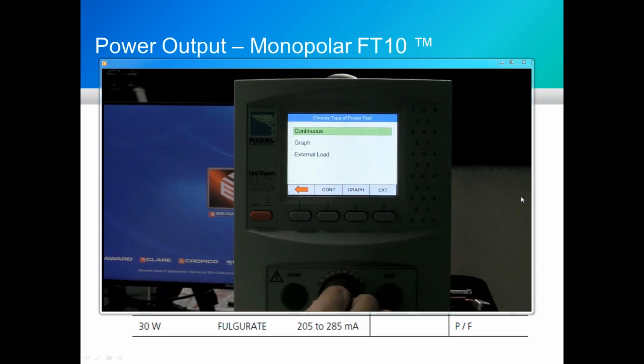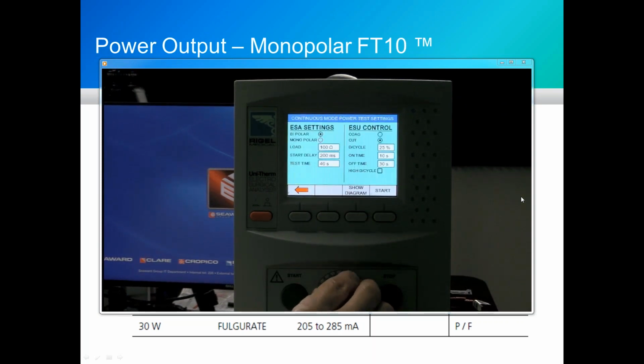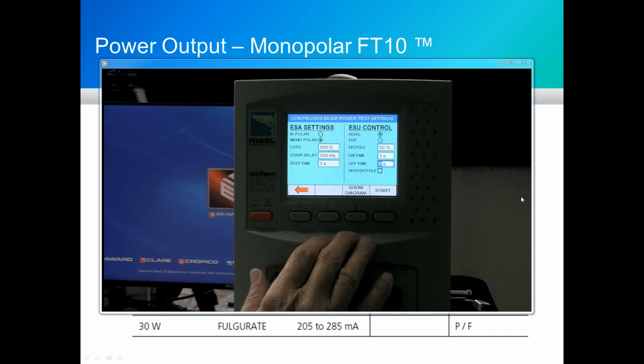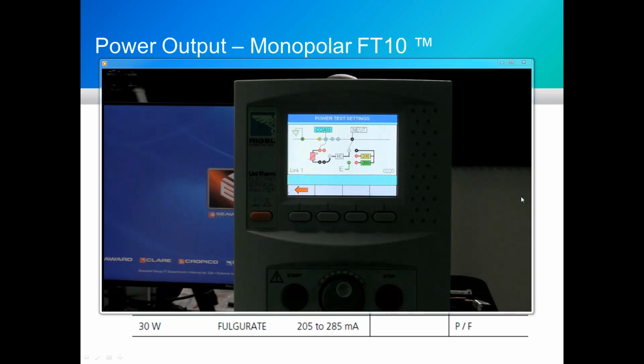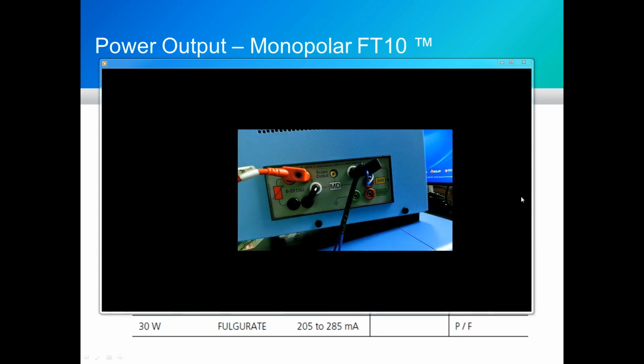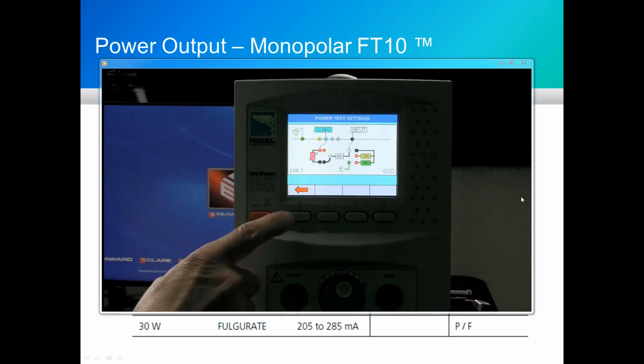Selecting power test, continuous power test, which is where with the Uni-Therm you spend the majority of your time. Setting my load resistance. Load resistance on this unit goes from 5 ohms up to 5,115 ohms in 5 ohm increments, as you saw. And it's rated for a full 500 watts continuous operation for a full minute, which is pretty heavy duty. I'm selecting coag. I'm selecting 5 seconds for my on time, 5 seconds for my off time. Once I get there, show diagram. We took a look at this earlier. So for my active electrode, through my resistor, through my current transformer, here's the connections on the side of the unit, and then back to the patient return.